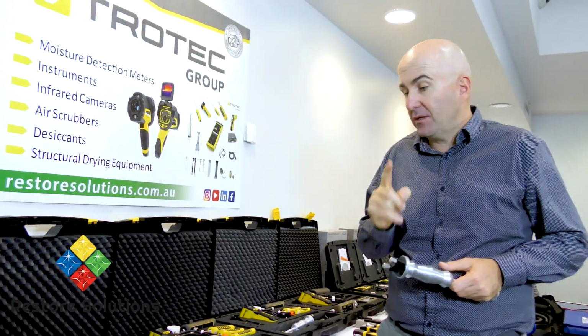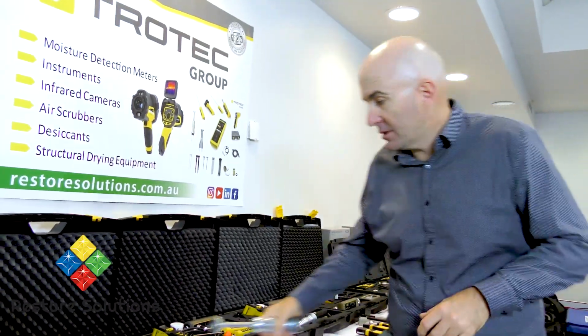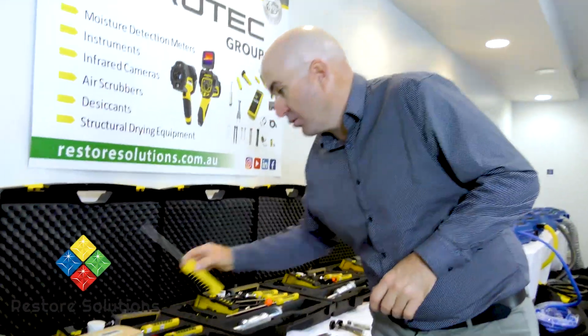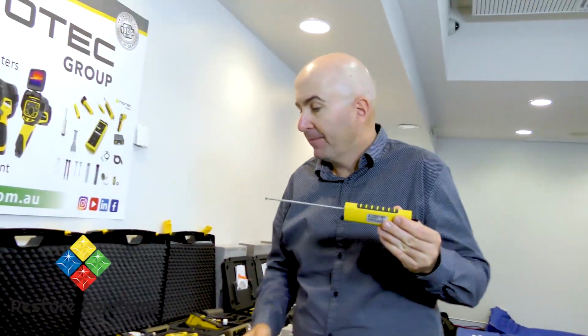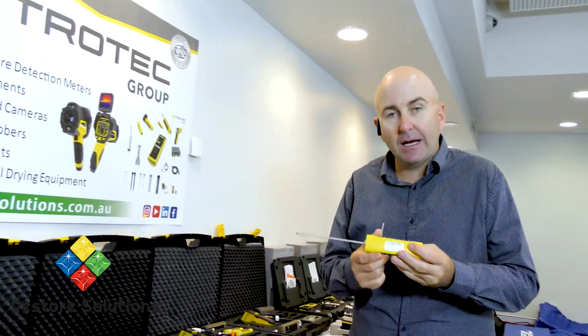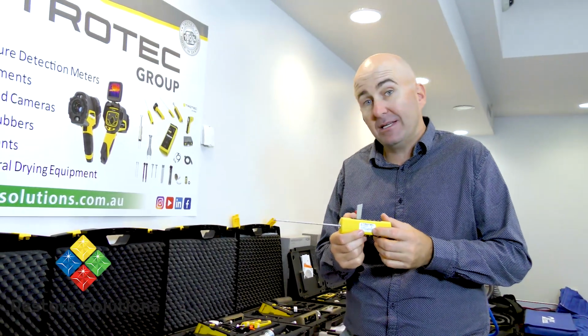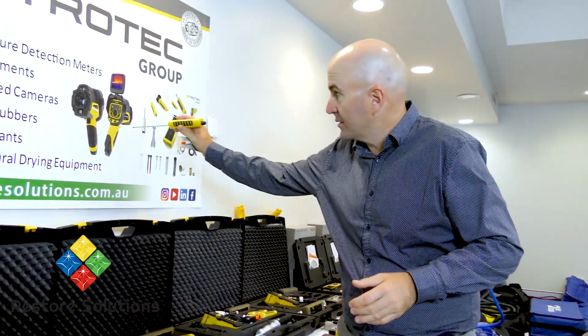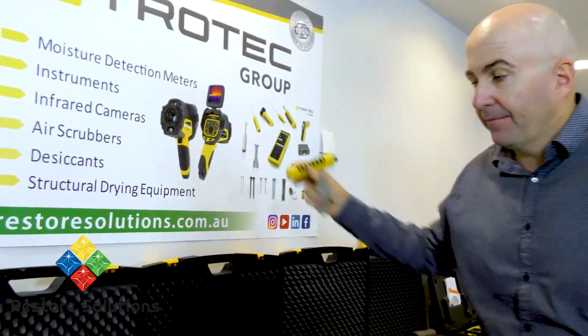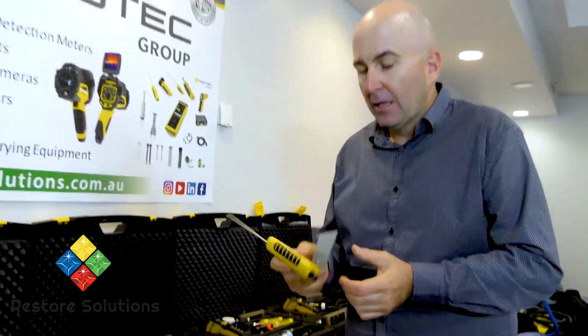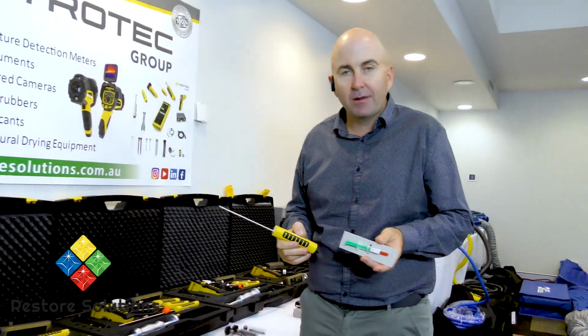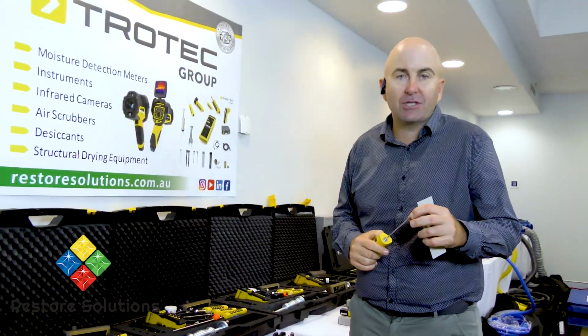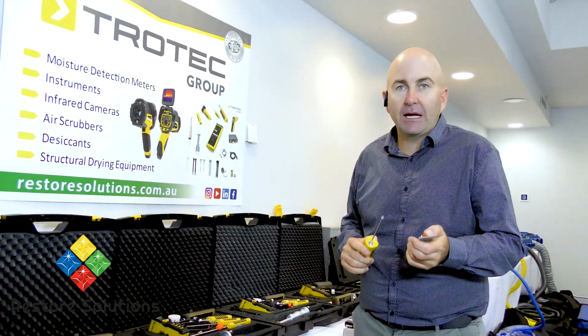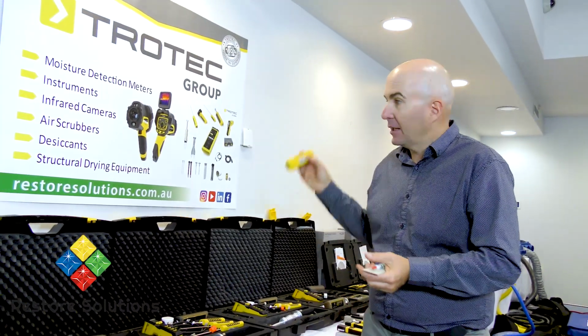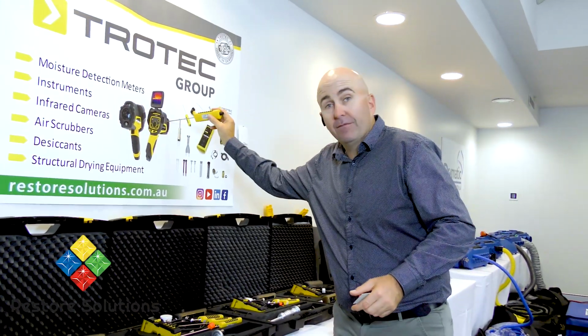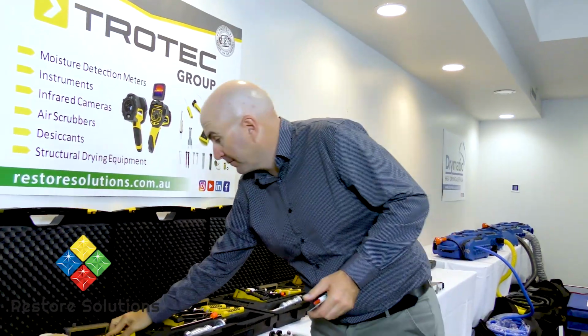You have to take your surface temperature first. This is a great way of taking your surface temperature. This is a surface temperature sensor, which you actually put on the surface to get a reading. Obviously, the cable goes back to your meter, and it comes with a little bit of goo. If you don't have a flat surface, and you need a really flat surface, this goo will help get that conductivity and give you that flat surface.